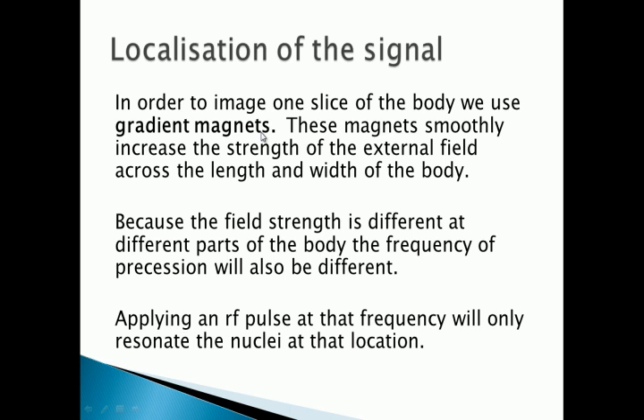The gradient magnets smoothly increase the strength of the field B0 from the feet towards the head, for example. The reason for doing this is that angular frequency and precession frequency both depend on the strength of the magnetic field, so we can change the frequency that the protons are precessing at for different parts of the body. The protons in the feet will be precessing at a slightly different frequency to those towards the chest. By targeting a particular slice using radio waves at a specific frequency — the frequency that just that slice is precessing at — we can make only those protons resonate and give us a signal.